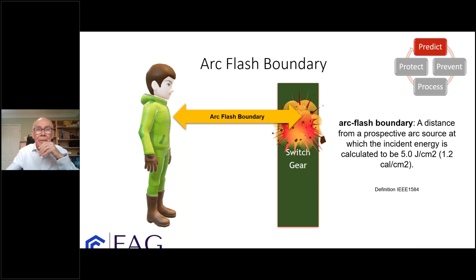What we're looking for is managing the risk of harm from arc flash, and this table categorises those risk reduction measures into the first one and most important one, which is dead working. It must be the principal prevention measure of any safe system of work - that we do things dead, or in electrically safe condition, as they may say in the States.